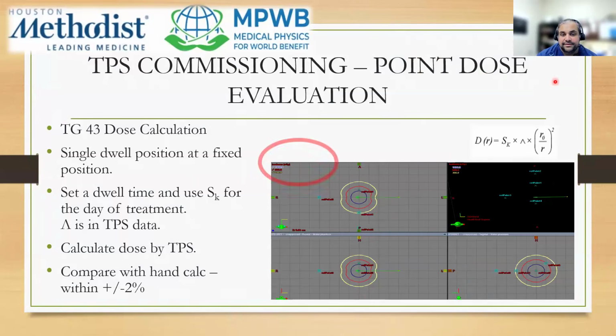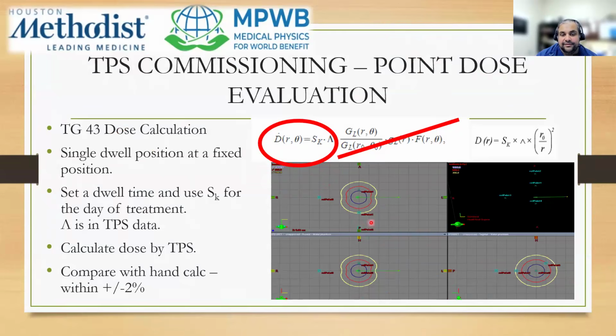A quick test for your TG43 calculation is to add an arbitrary dose point at about 1 cm, where your geometry factor and your anisotropy factor all become unity. You already know your air kerma strength for the day of the treatment. The dose rate constant is what you have in your system, and if you multiply those two numbers, you can do a quick hand calculation at that distance. R naught is of course 1, so it is 1 over R squared. At that distance, the dose that your TPS calculates should be within plus or minus 2%. And this is a test that, ideally, you should do after every source exchange.